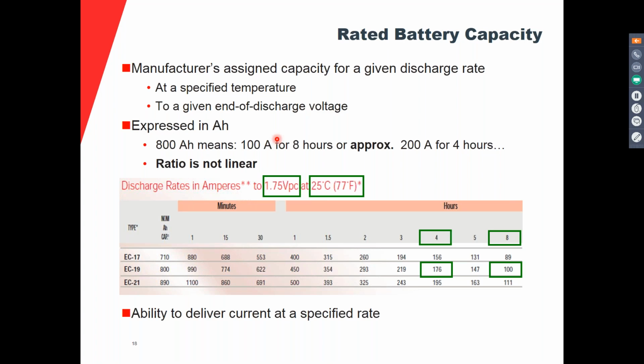The rated capacity of a battery is given in amp hours. For example, a battery that has 800 amp hour as a rating means that this battery can deliver 100 amps continuously for 8 hours. You would think that this will be a linear ratio. Well, it is not. It doesn't mean that the battery can do 200 amps for 4 hours, which will also be 800. This doesn't happen with the batteries.